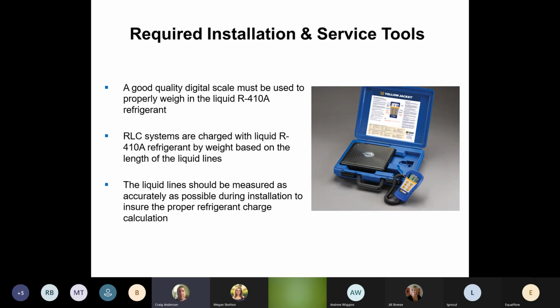If you talk to a service guy on the phone and you're telling him, I added some gas, I took some gas out, he's going to tell you to take it out and weigh it in. So save the headaches, take it out, weigh it in, you know that's proper, and let's move on. When we get into the modulating air conditioners and stuff like that, the only thing your gauges are telling you at that point is the compressor's running. We have gas in it and the compressor's running. That's all we can really check. So make sure you got a scale in your truck. It's the only way to do it properly.